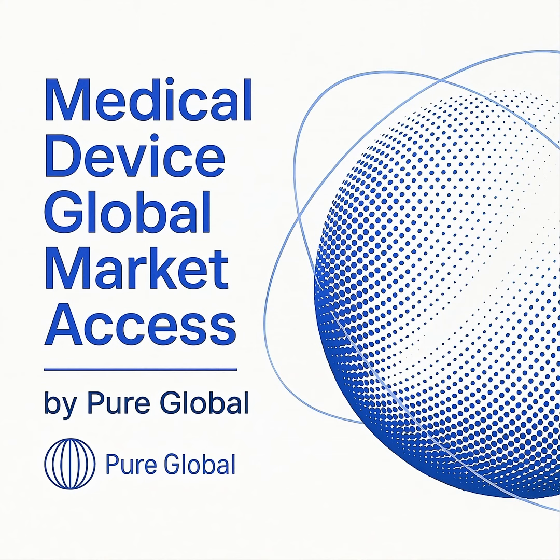This can be done through two main pathways. The first is a literature-based approach, which involves a systematic review of existing scientific literature on your device or an equivalent device. Proving equivalence has become more stringent under the MDR, requiring a thorough analysis of technical, biological, and clinical characteristics as detailed in guidance documents like MDCG 2020-5.